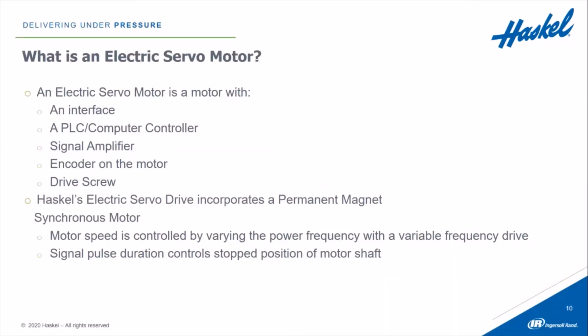I've had a number of people ask me, what is an electric servo motor? An electric servo motor is a motor that has an interface that allows an operator to control the motor, has a PLC or a computer controller, has a signal amplifier, has an encoder on the motor, and a drive screw. Haskel's electric servo drive motor incorporates a permanent magnet synchronous motor. The motor speed is controlled by varying the power frequency using a variable frequency drive, and the stop position is controlled by a signal pulse, by controlling the duration of the signal pulses.